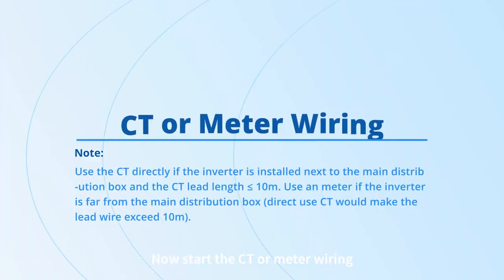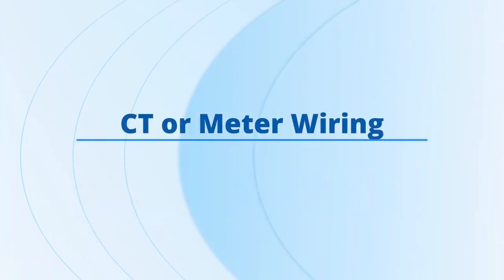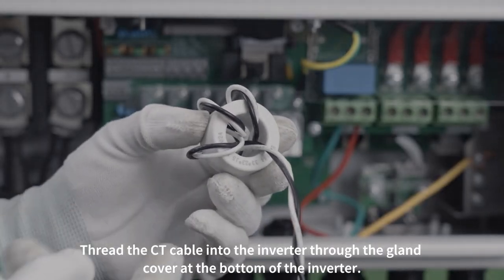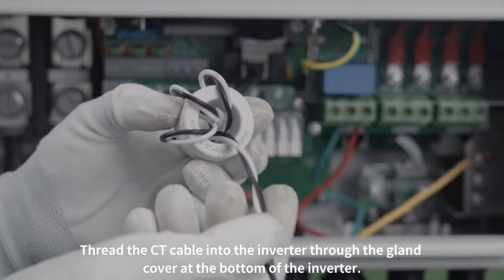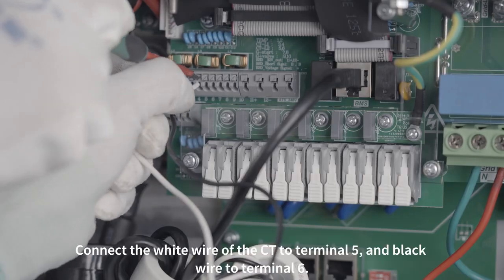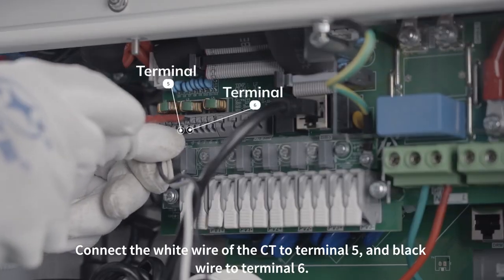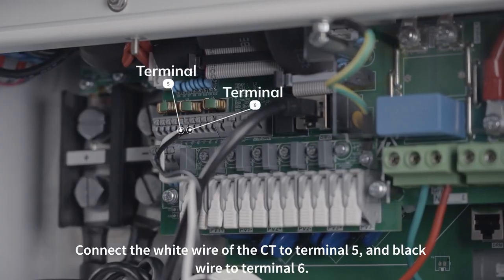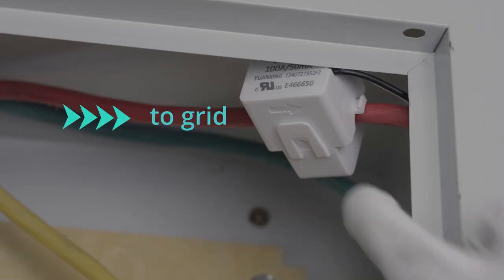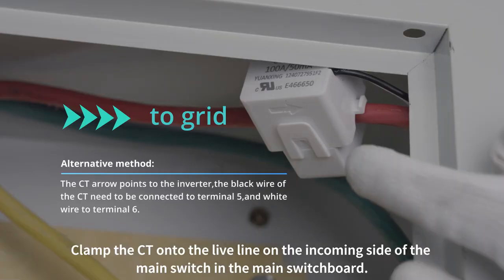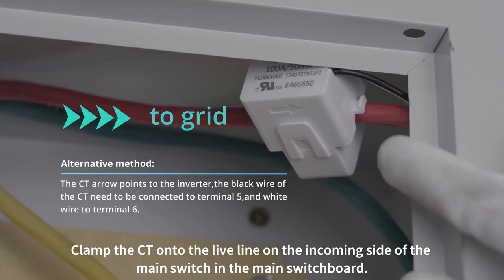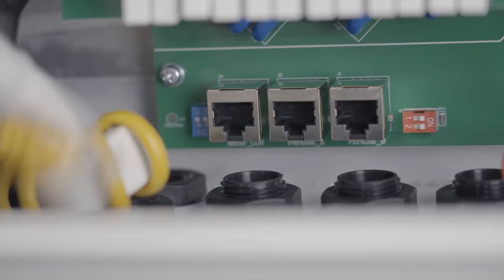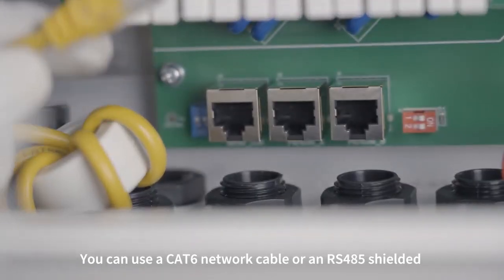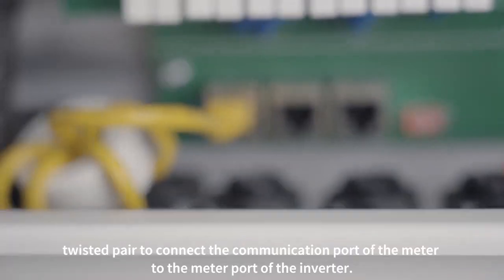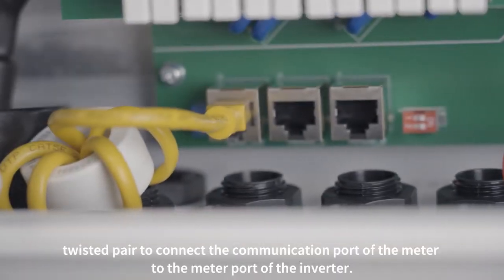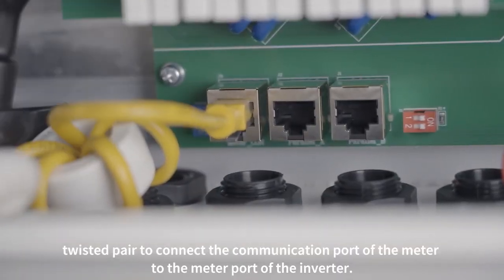Now start the CT or meter wiring. Thread the CT cable into the inverter through the gland cover at the bottom of the inverter. Connect the white wire of the CT to terminal 5, and black wire to terminal 6. Clamp the CT onto the live line on the incoming side of the main switch in the main switchboard. You can use a Cat6 network cable or an RS485 shielded twisted pair to connect the communication port of the meter to the meter port of the inverter.